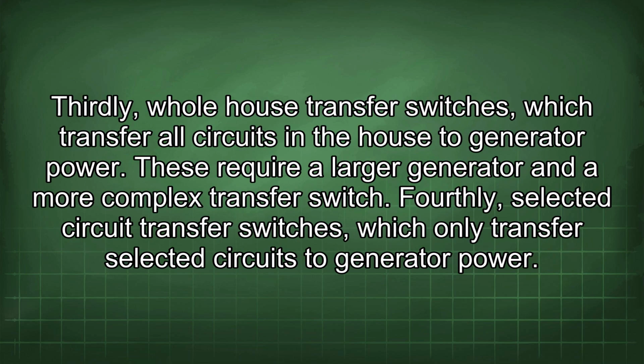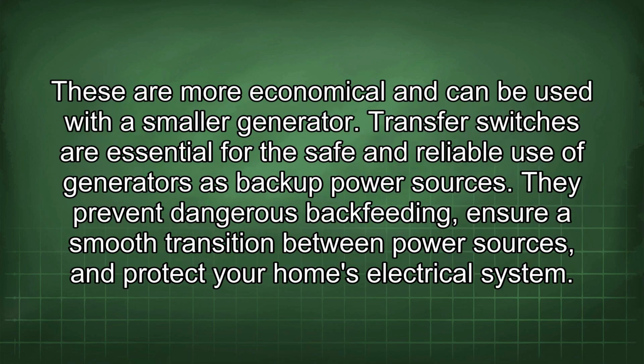Thirdly, whole house transfer switches, which transfer all circuits in the house to generator power. These require a larger generator and a more complex transfer switch. Fourthly, selected circuit transfer switches, which only transfer selected circuits to generator power. These are more economical and can be used with a smaller generator.